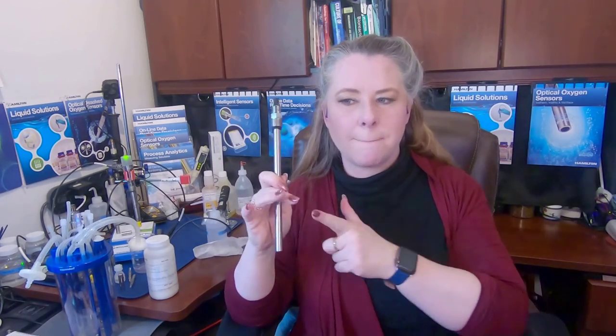However, just to give roundabout prices that are not exactly right, let's say a polarographic probe is a $1,000 sensor. In 1 year, and this is really conservative, pretty low consumption, you will need to replace the membrane cap 3 to 4 times, about every quarter. So you need 4 caps a year. You will need to replace the electrolyte every single run. Let's pretend your runs are 2 weeks long, so you're doing 2 a month, so 24 a year. You're going to need to replace the cathode assembly roughly every 6 months with standard use. So your annual cost, and this does not take into account labor, this is just parts, is probably about $4,000 for this probe in a year of usage.